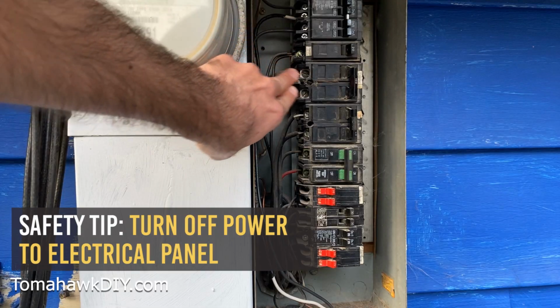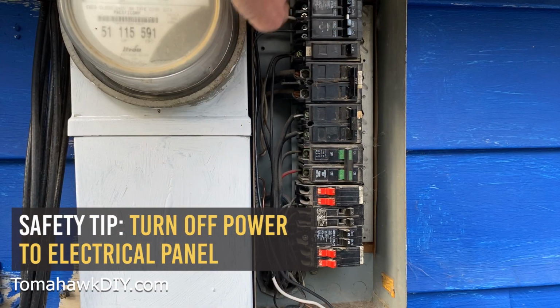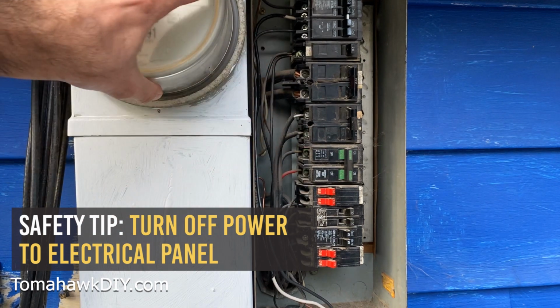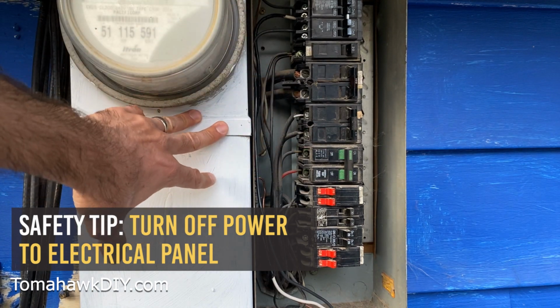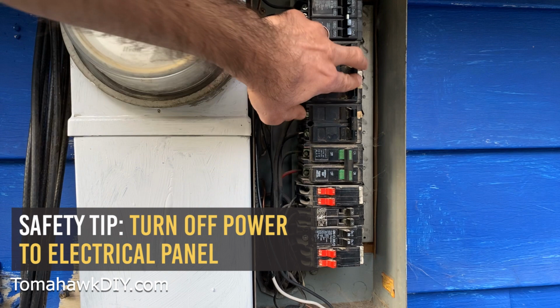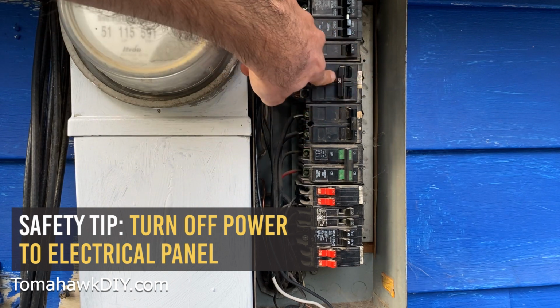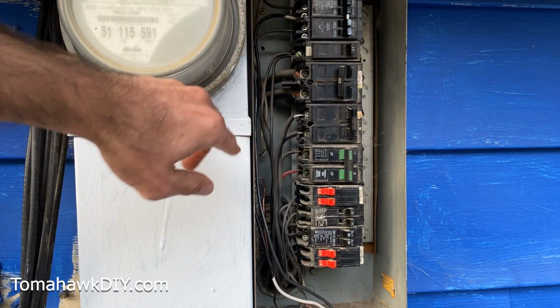For safety, you got to turn power off to the entire panel here, because there's not a disconnect—this feeds directly from the main incoming power from the power company. When we turn off the main breaker, 100 amps here, that killed power to the entire house.